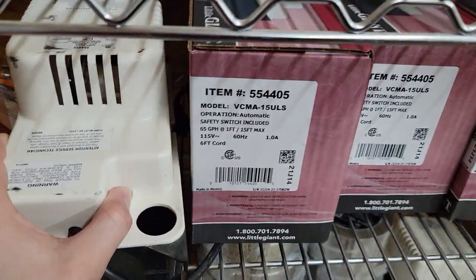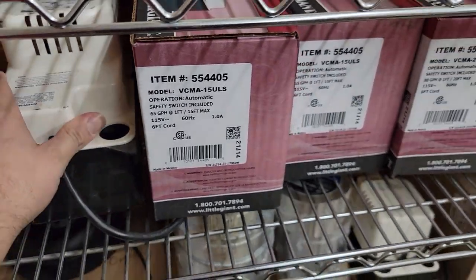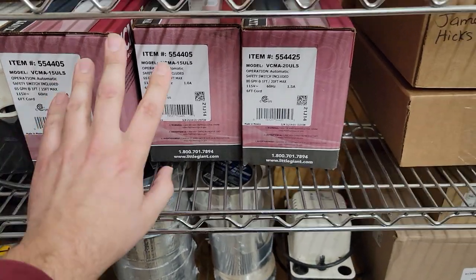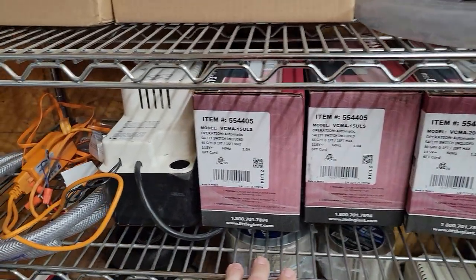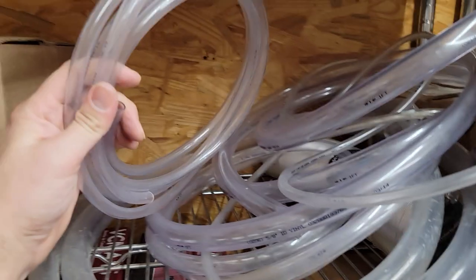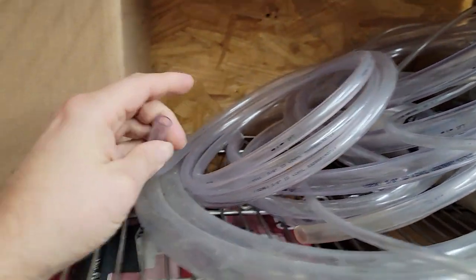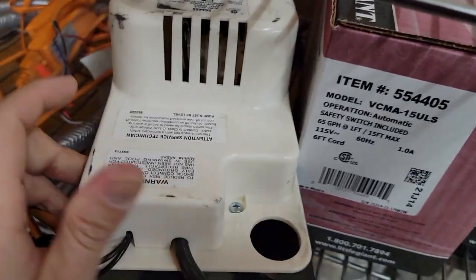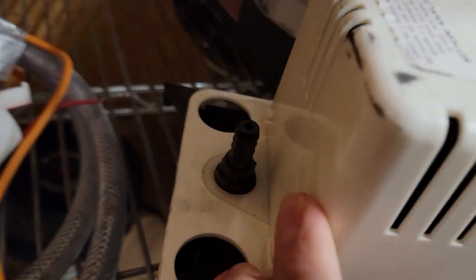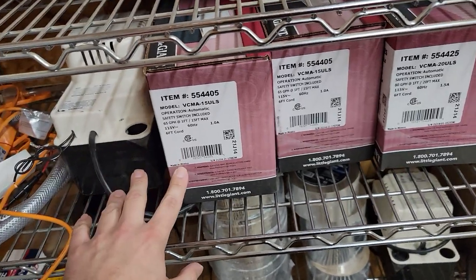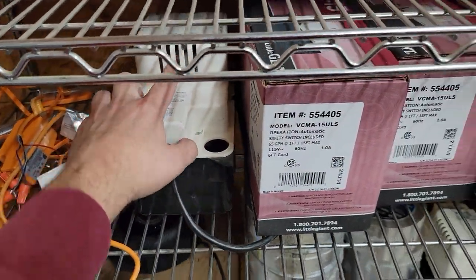Ooh, I almost forgot, condensate pumps. You might have to have a condensate pump. You got 115 volt condensate pumps. You've also got 230 volt condensate pumps. You may need to keep some drain tube on your van, 3/8 drain tube. This is what connects to this condensate pump here. I'll show you that. See right there? So you may need to keep a condensate pump on your van. They either need to be cleaned or the motors burn up.